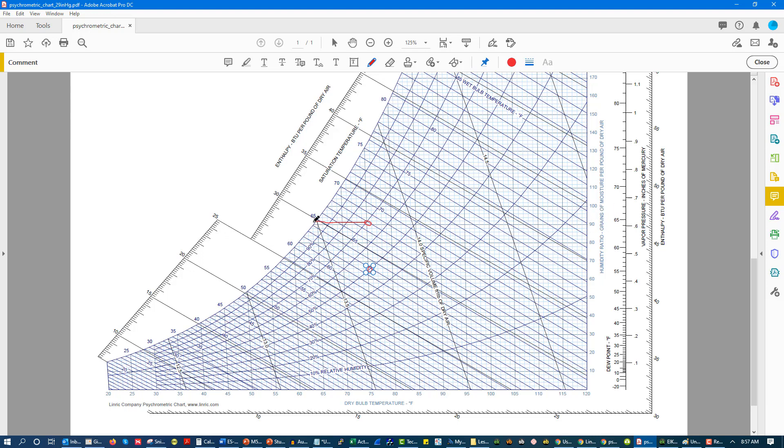Now what's going to happen as we continue to cool the air and we drive it down to maybe like 55 degrees, now our humidity ratio has dropped. So we've enacted cooling to the point where we are hitting dew point and we're driving it down to 55 degrees.